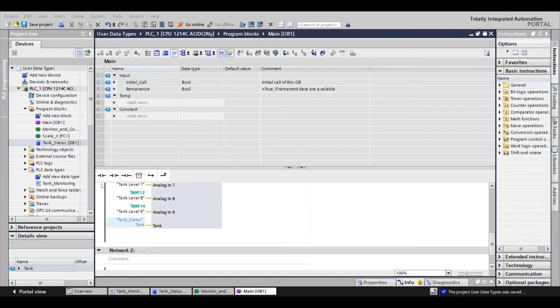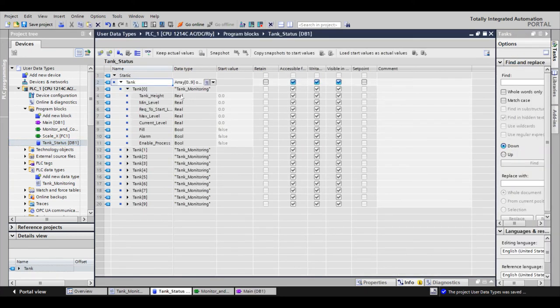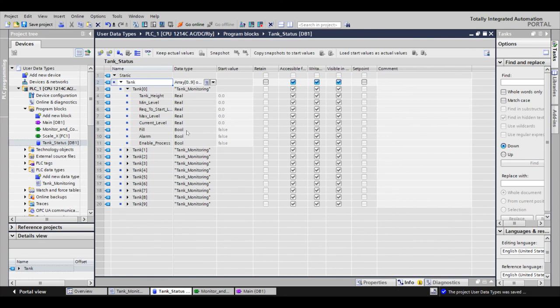This becomes especially convenient when it comes time to commission your project. If you have 10 tanks with varying sizes, you can come into the single data block, change the tank height, change the min level for each tank in one place. This is also helpful when it comes to face plates for the HMIs, but I'll cover that in a different video.